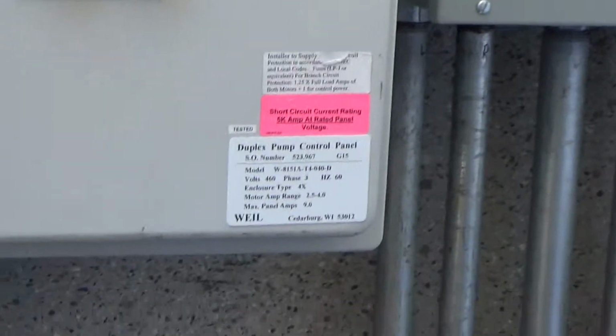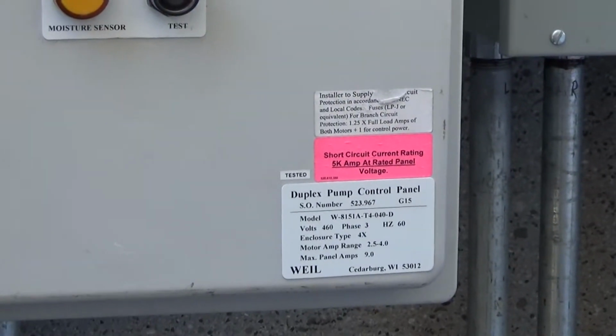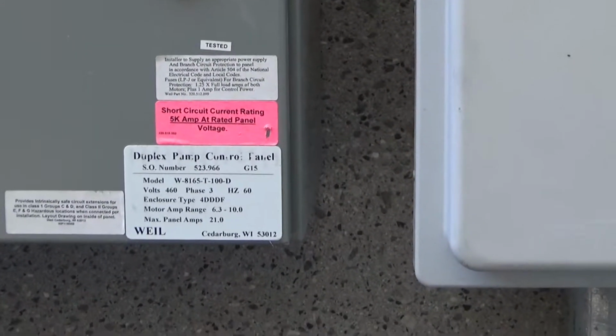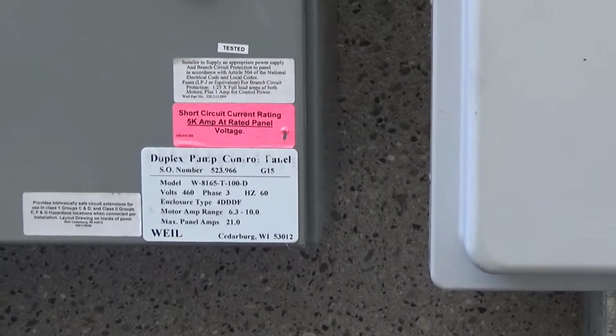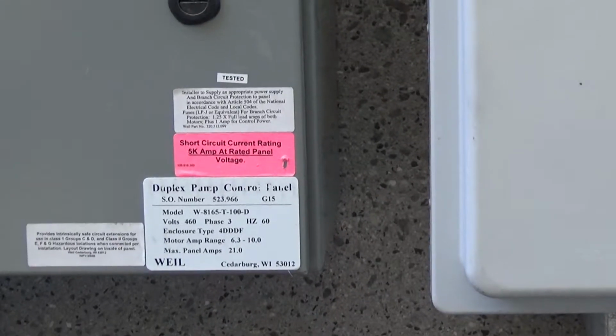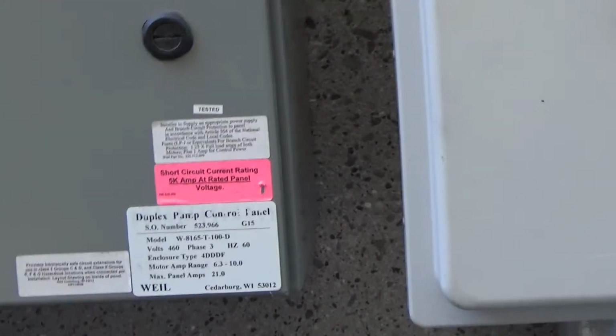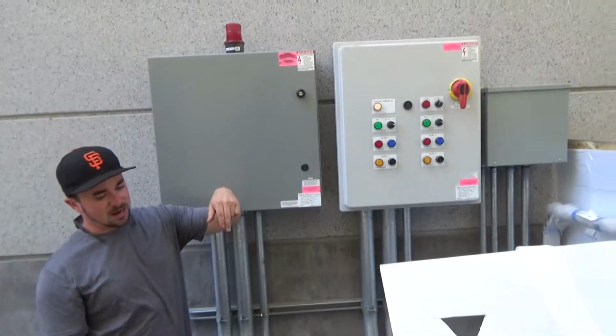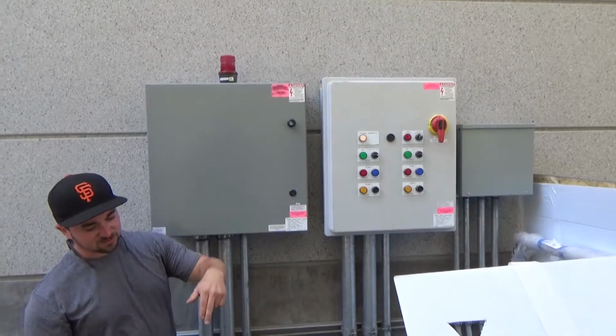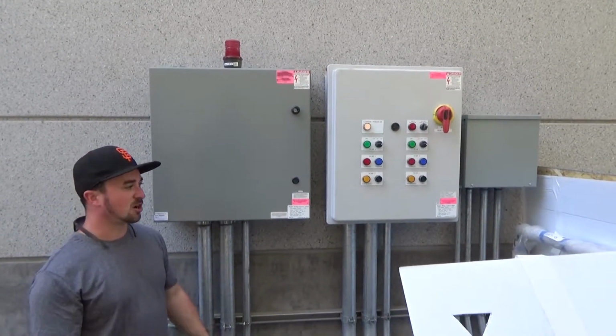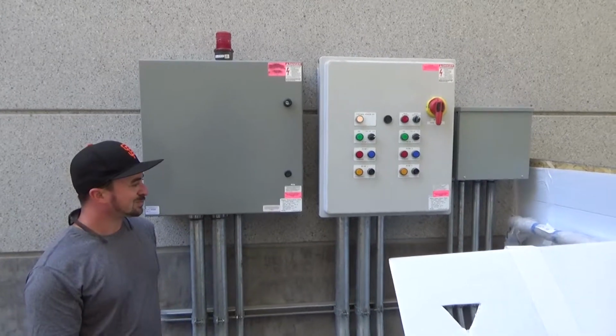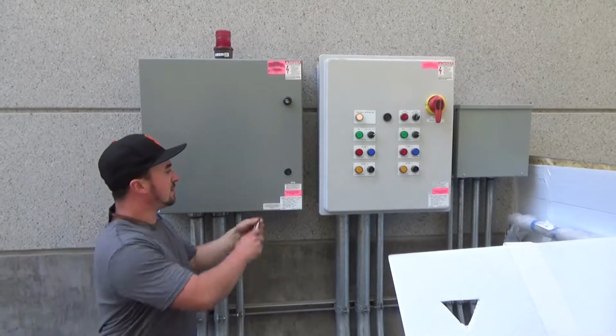So, I mean, it's super basic. You have 4 floats, like I said, 2 pumps. They're going to switch back and forth, so the pit's going to fill up. First float makes, nothing happens. Second float makes, a pump comes on, pumps it down. Second float's going to break, or it's going to keep pumping, and then the first float will break, and then it'll shut off. Pretty much like inside of this one.